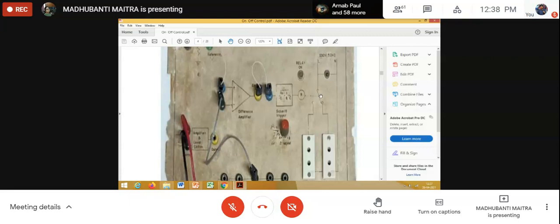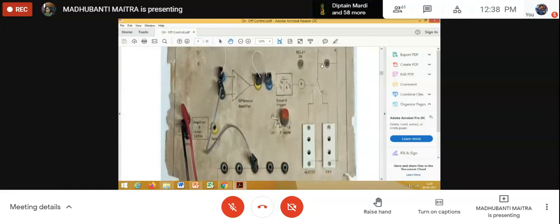So, what will happen? Finally, the fan will get disconnected from the circuit, and since now this contact is closed, and this contact is open, hence the heater will get connected across the phase. This is our phase. So the heater will get the rated supply and heater will be connected in the circuit. Have you understood this?